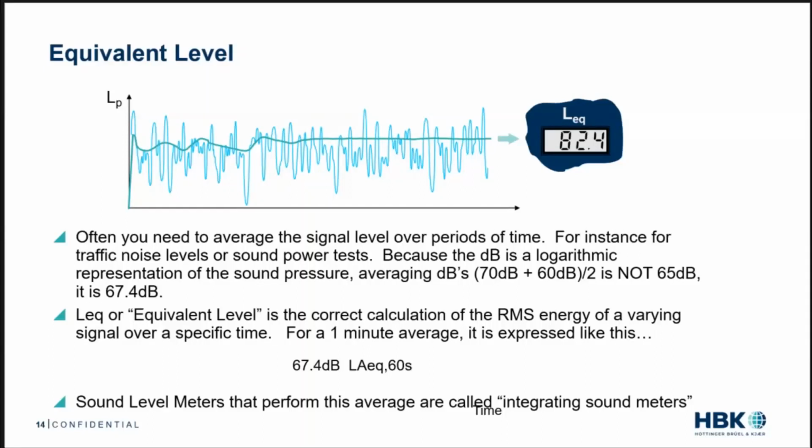Instead, we want a long-term average of the noise level, perhaps 15-minute intervals. Here we'll use the integrating functionality of the meter, where we assess and update the RMS value instantly with time. This parameter is called the equivalent level.